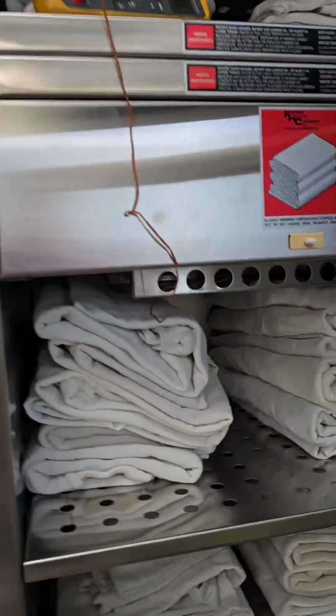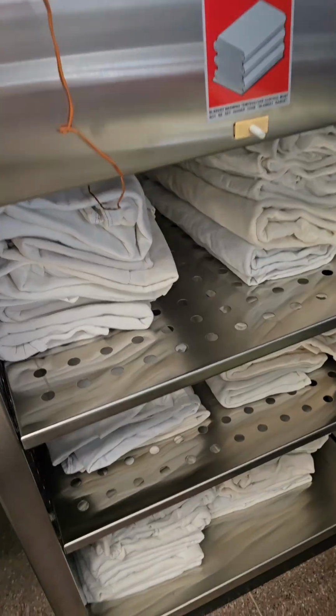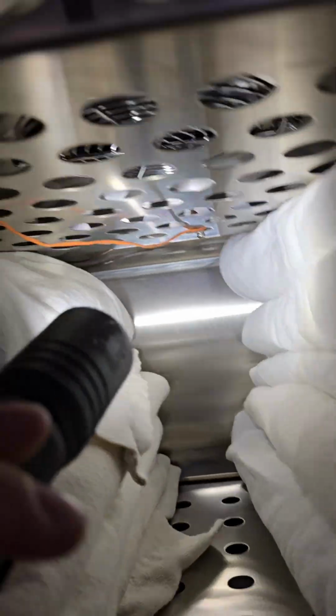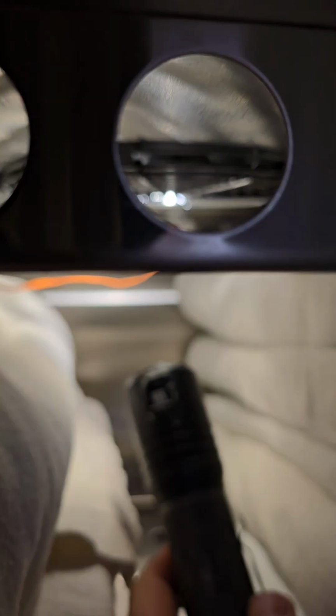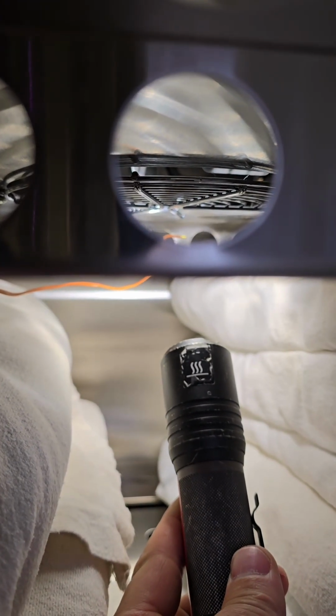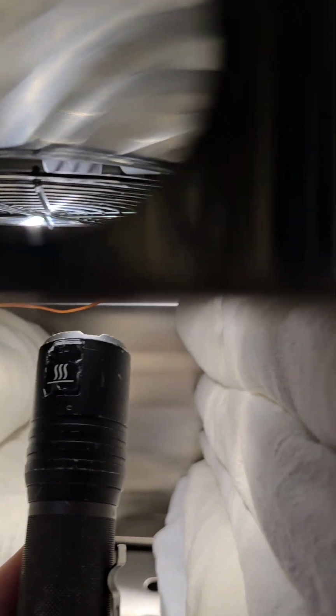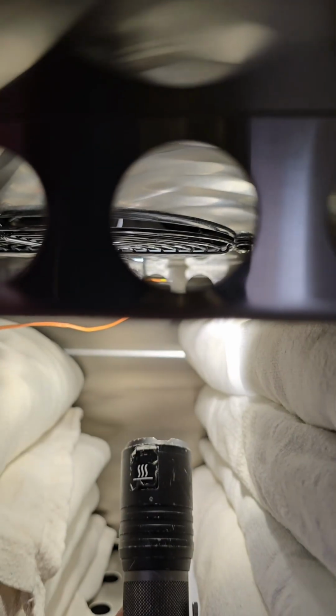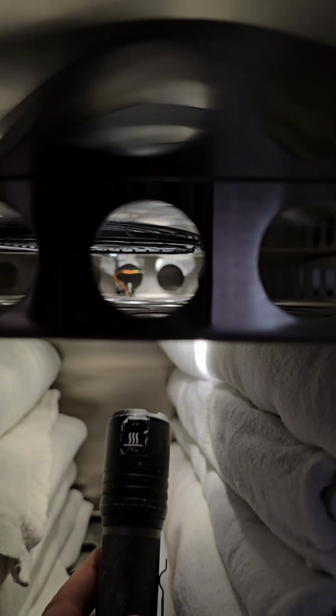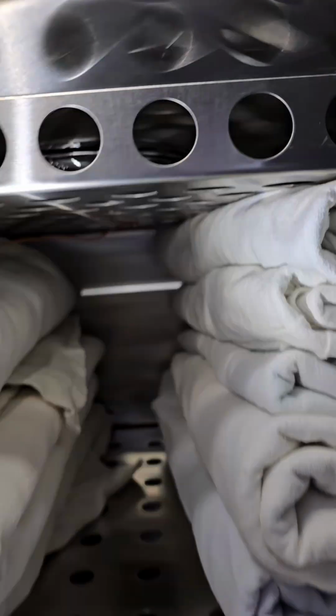You want to be as close to the device's thermometer as possible without your tip touching any metal. So on these FHC MacMedicals, your temp probe is inside this little cabinet here. If you see that right there, that guy in the middle, that's your probe. There's my probe. See my tip not touching anything. Sorry, my camera's not. Okay, right there. See my probe, the brown yellow guy right there, directly above the unit's probe.